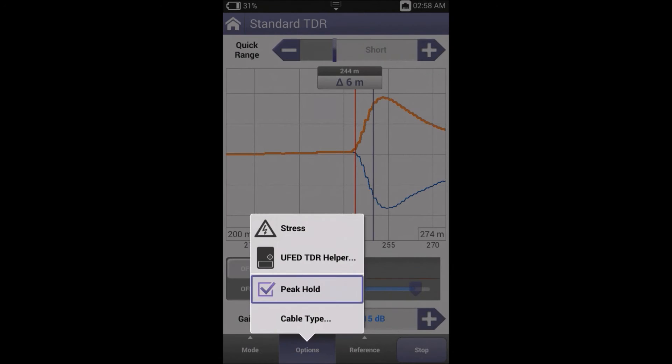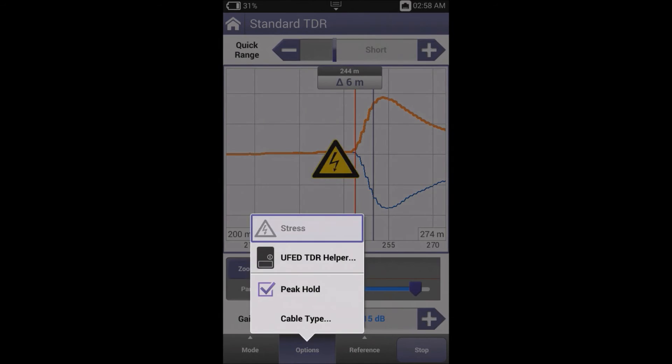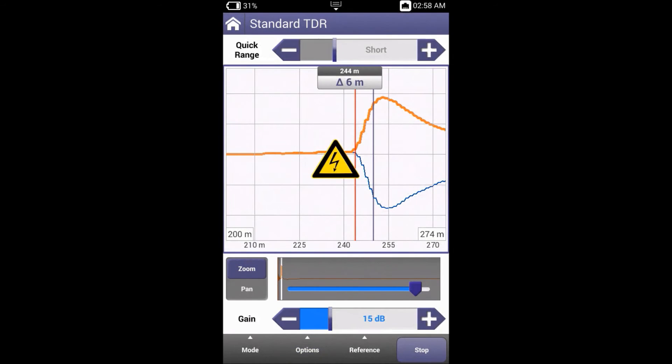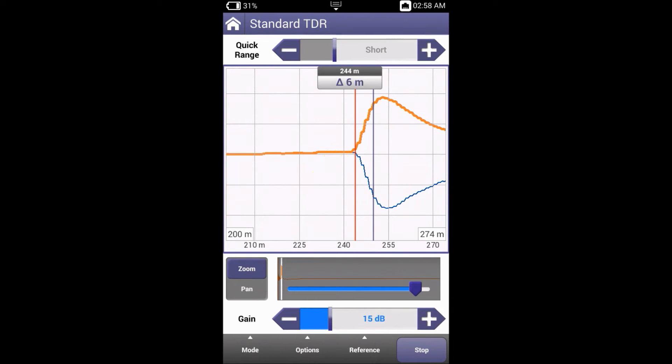Stress, when activated, momentarily stops the TDR and connects the ONX leakage ohmmeter for a number of seconds, and instantly returns to the TDR. The leakage ohmmeter applies approximately 120 volts in dual polarity, attempting to disrupt the fault resistance and make its location viewable on the trace.